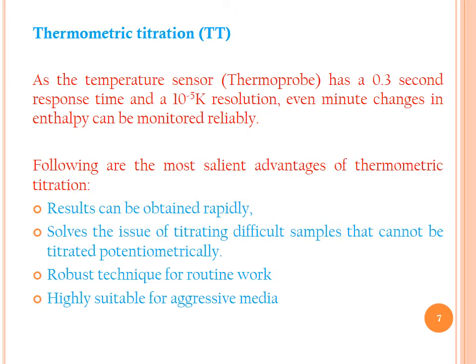The thermoprobe temperature sensor has a 0.3-second response time and a resolution of 10⁻⁵ Kelvin. With this high resolution, even minute changes in enthalpy can be monitored reliably. This is the advantage of TT over manual titration methods.